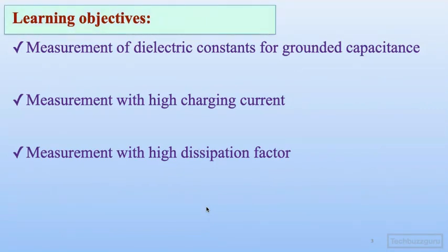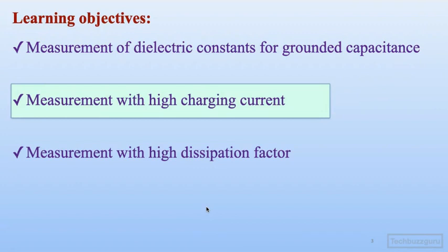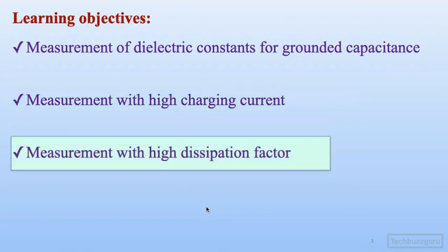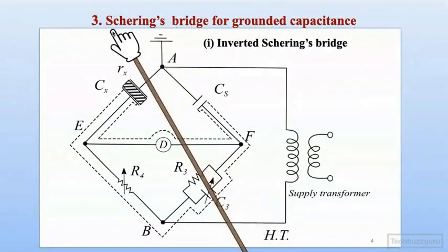The learning objectives for this topic are: first, to measure dielectric constants with respect to grounded capacitances such as underground cables whose outer coating is at ground potential; second, measurement with respect to high charging currents from cables and capacitor banks; and third, measurement with high dissipation factor. So three different versions of the Schering bridge will be considered.